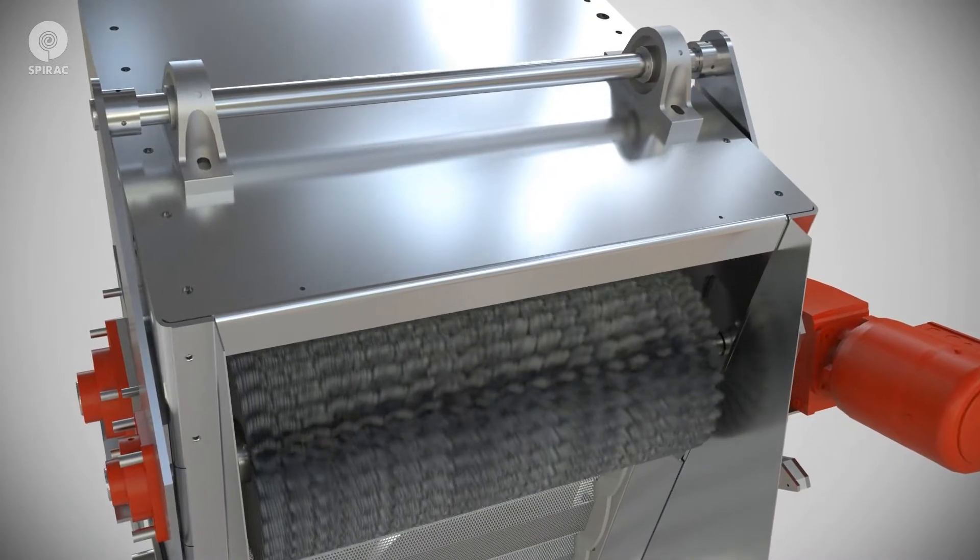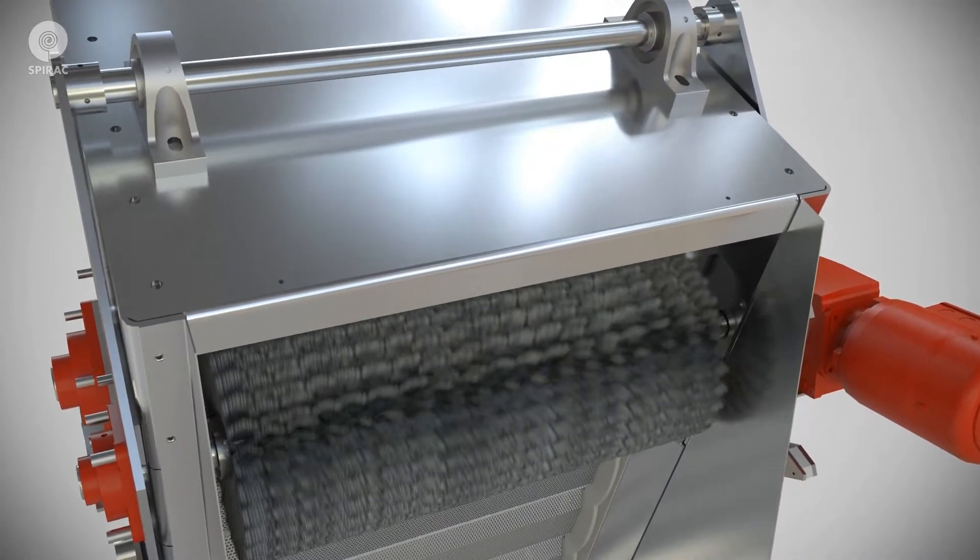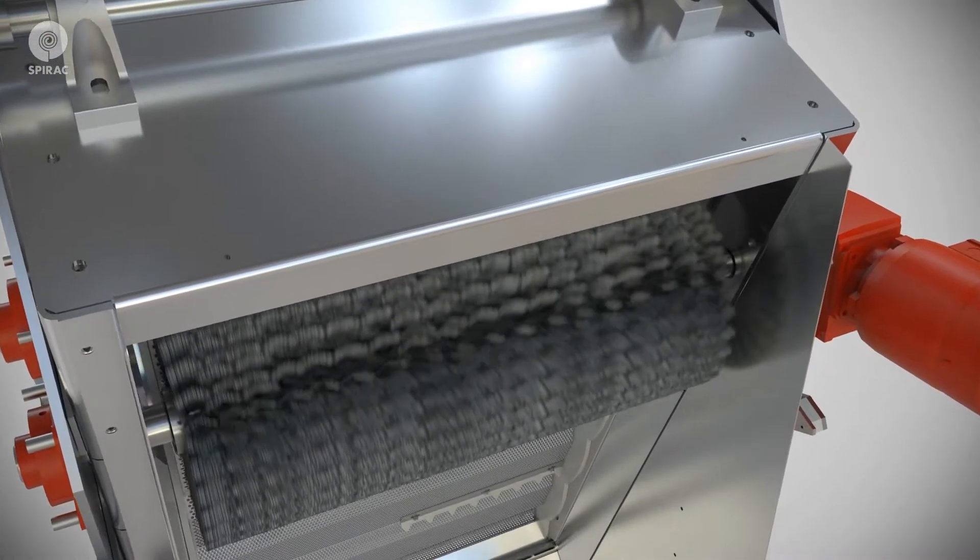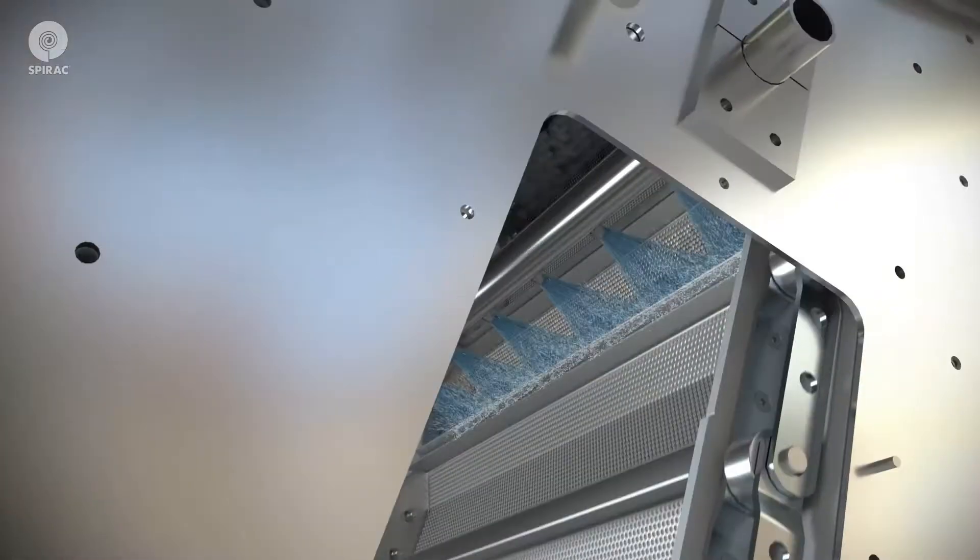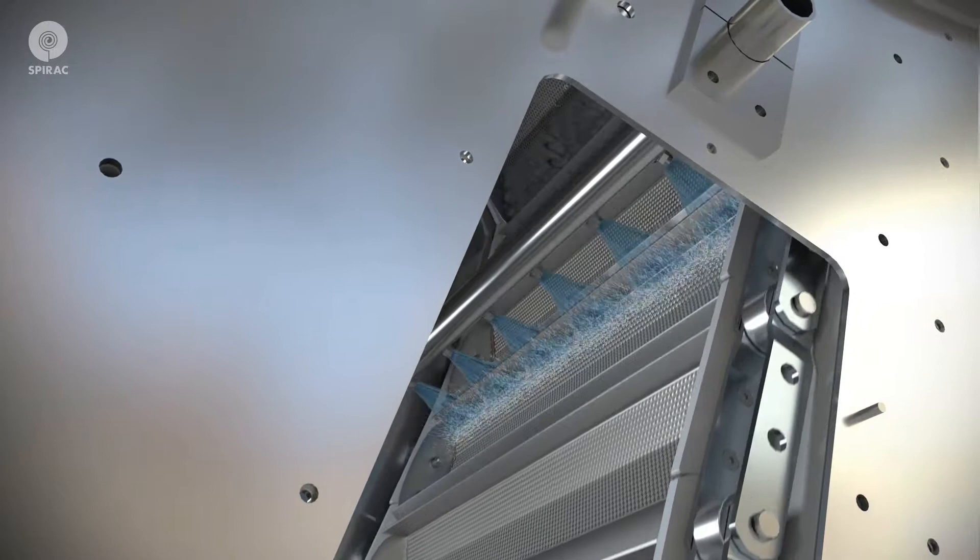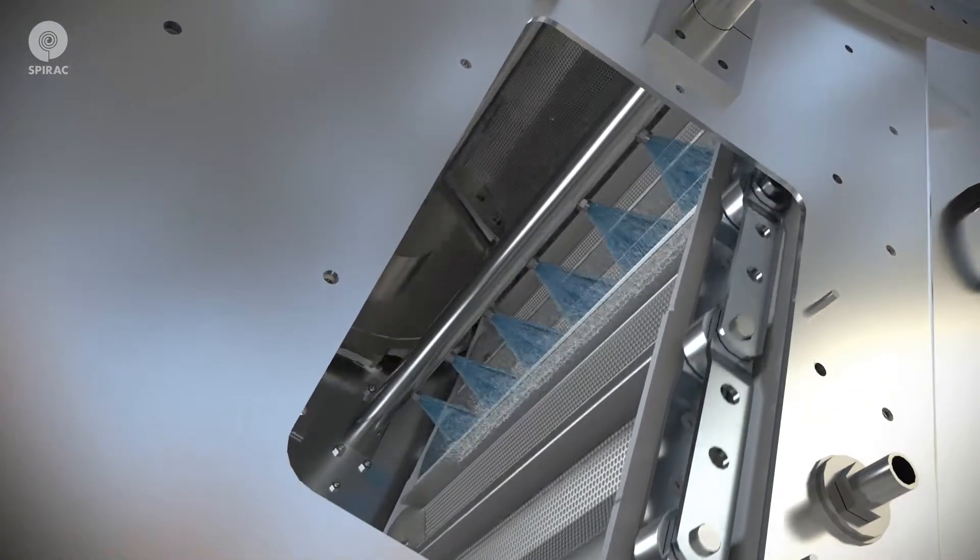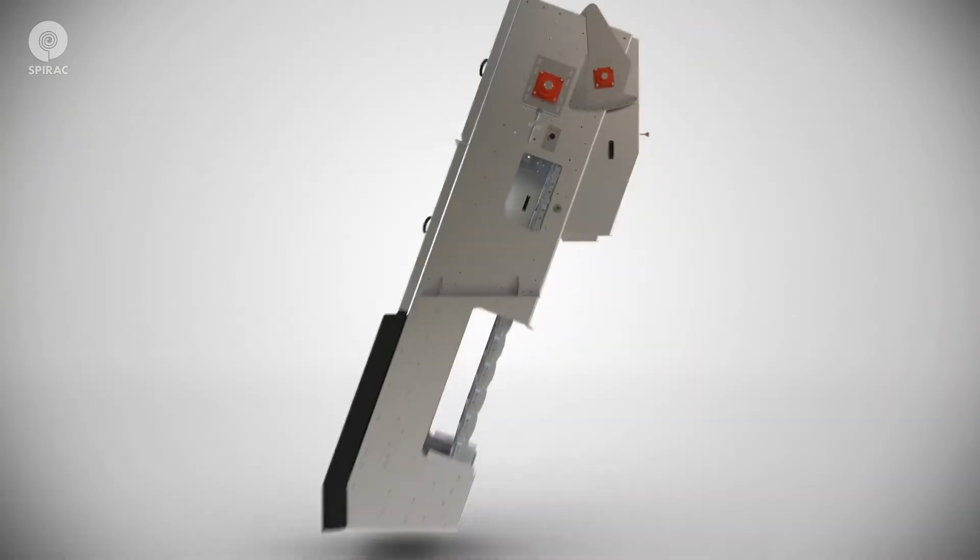FineGuard uses a two-stage panel cleaning process. First stage includes a self-adjusting rotating brush, which removes most of the debris. Second stage uses water jets to prevent screen panels from being blinded by hair pinning and rag stapling. The fully retractable spray bar allows cleaning if necessary.